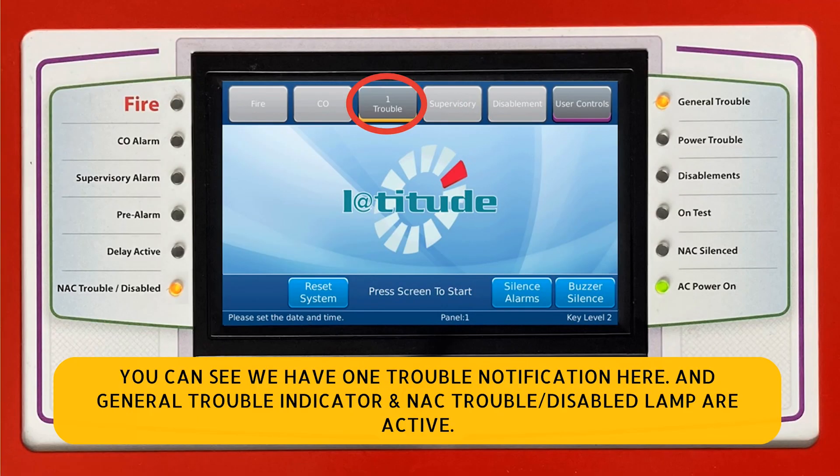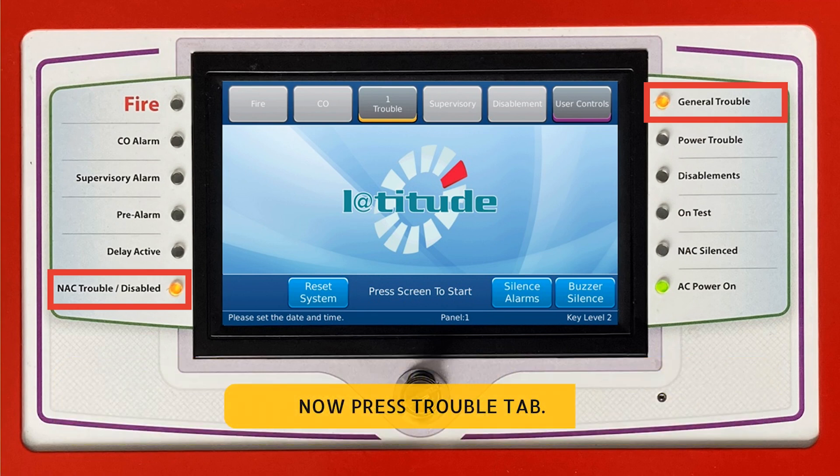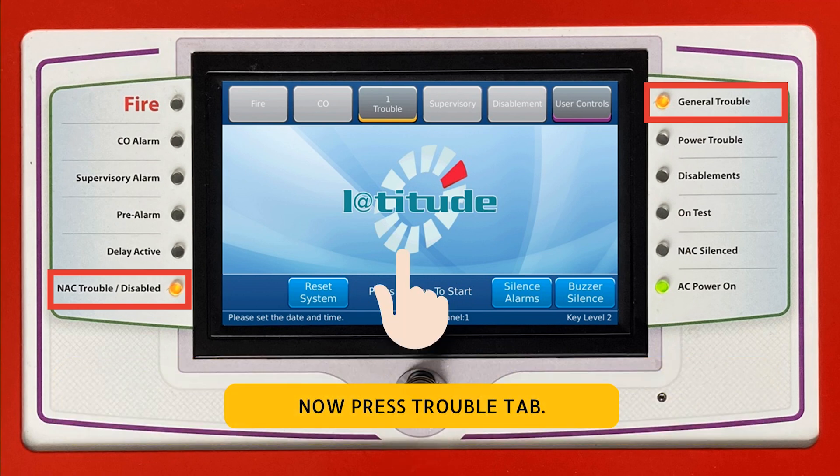Let's take a closer look. You can see we have one trouble notification here, and the general trouble indicator and NAC trouble disabled lamps are active. Now press the trouble tab.